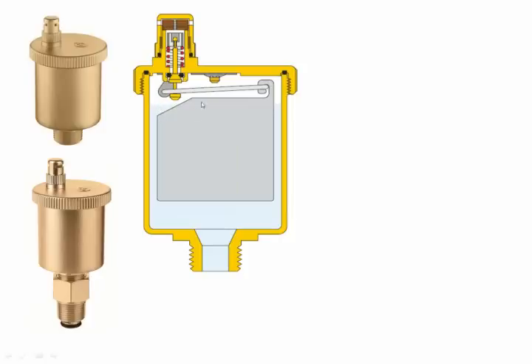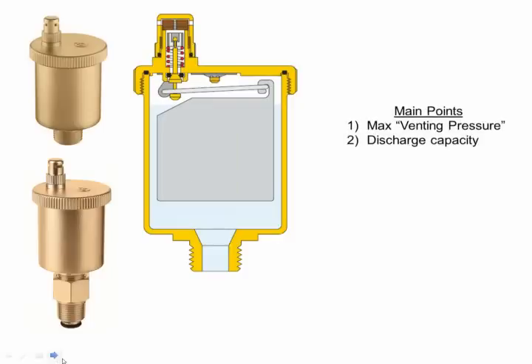The float is not sending air out of the system. What happens is air bubbles go into the float. This air column starts to increase, which drops the water column. The float drops with it, and because it's hooked to a pivot arm, this little needle valve pulls down, and eventually you have released the air to the atmosphere. It pushes the air out, the float goes back up, and that process continues over and over again until all the air is out of the air vent.